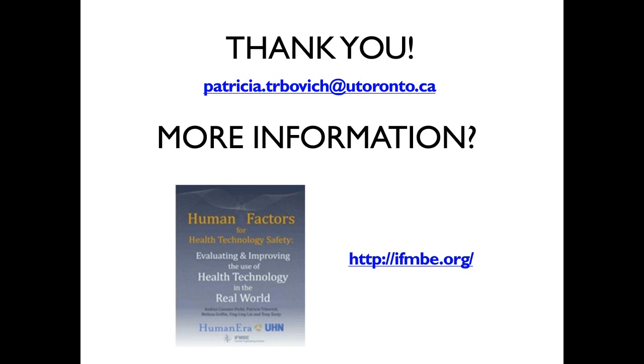Not only does it influence the decision, but it also helps clinicians with the buy-in. So if they've seen that they've had a say in the device that they're going to be expected to use, then the buy-in later is much easier. Also, it helps us understand where training needs to be focused when we introduce these systems. And there have been times when, because of the usability testing, we found that none of the 3 shortlisted vendors met the necessary requirements, and so we've decided not to go forward with the purchase at all. We know that we're stuck with these technologies. They're expensive, and we're stuck with them for many years, so doing this type of testing, which is not very expensive, can go a long way.